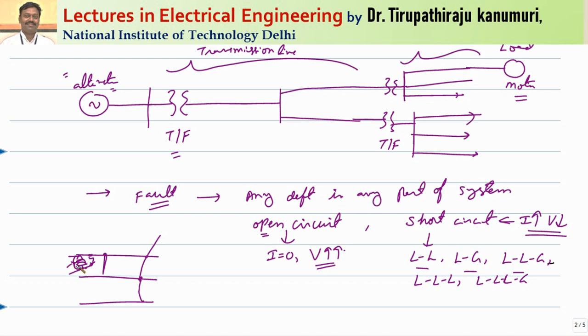One more case in transmission lines is the joint of conductors. Sometimes this joint will break. When the joint breaks between two towers, the conductor will fall on the ground, leading to a ground fault or short circuit fault. If the joint is near the tower and no conductor has fallen on the ground, it leads to an open circuit fault. Similar is the case for cables, where insulator failure may also lead to problems.